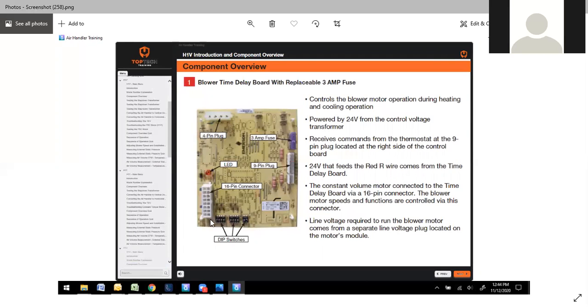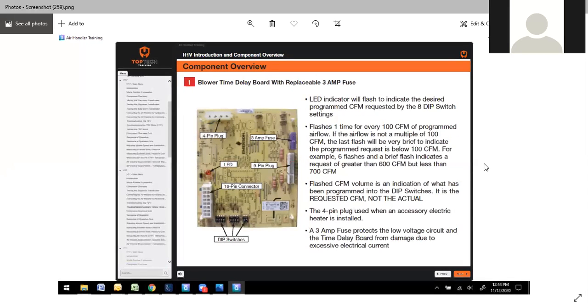You'll see you have a series of dip switches down here as well. You will have some LED lights on here. Since this is non-communicating, the LEDs will kind of give you an idea of what's going on. LED will flash to indicate the desired programmed CFM requested by the 8 dip switch settings. It'll flash one time for every 100 CFM of programmed airflow. If the airflow is not a multiple of 100 CFM, the last flash will be very brief to indicate the program request is below the 100. For example, 6 flashes and a brief flash indicate a request of greater than 600, but less than 700.